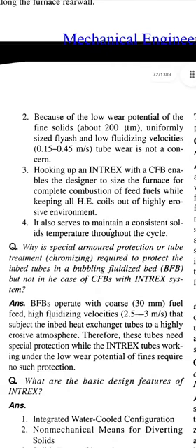Hooking up an Intrex with the CFB enables the designer to size the furnace for complete combustion of feed fuels, while keeping all HE coils out of highly erosive environment. It also serves to maintain a consistent solid temperature throughout the cycle.